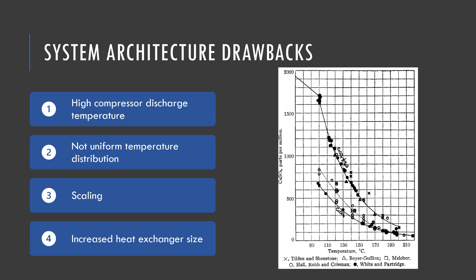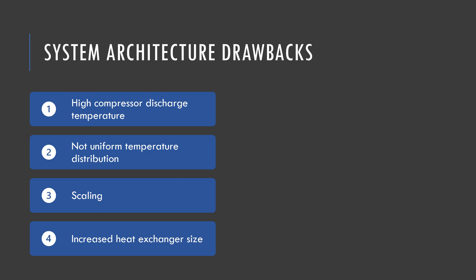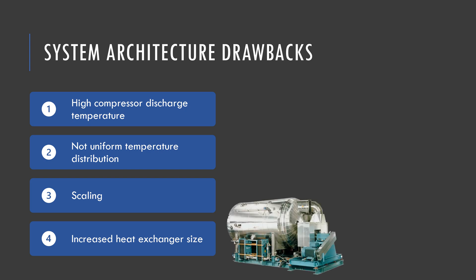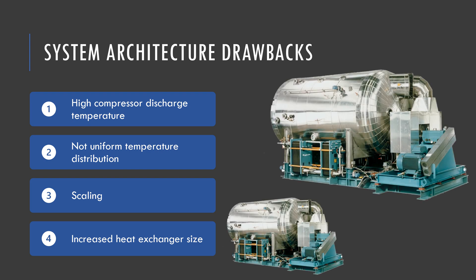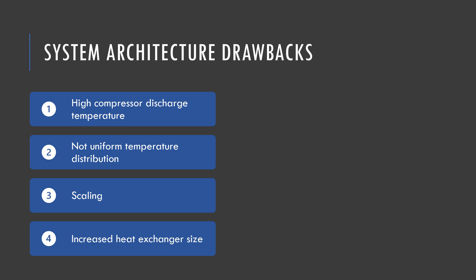All of these consequences related to the high discharge temperature limit the saturated temperature rise in the compressor to between 2 to 5 degrees Celsius, therefore reducing the mean temperature difference in the falling film evaporator and increasing its size. Resolving the high discharge temperature issue of the compressor will create a cascade of improvements leading to efficient operation and design.